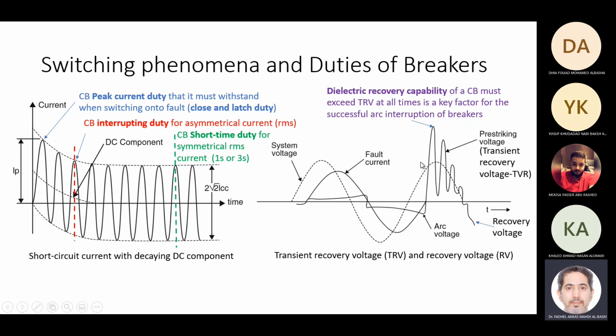There is also something related to the voltage. Suppose a fault occurs; this is the system voltage, the dotted line, and the current is here. Suppose now the breaker is tripped, so it's opened. You interrupt a current. So this is the fault current before the breaker opens. The breaker command is given here where you want it to open. These small ones represent the voltage at the contacts while it is opening.